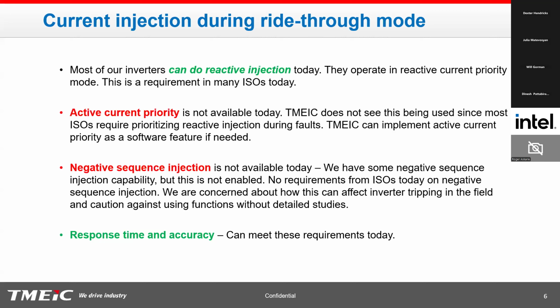On response time and accuracy, there are accuracy requirements, I think plus 10% and minus 2.5%, as well as a time requirement for these functions, I think 2.5 cycles to 4 cycles for steady state. We believe we can meet these requirements today with our existing inverters, even in the field. We don't have any problems in that regard on existing or new inverters. Whatever I'm saying about current injection applies to most of our existing inverters in the field as well as newer inverters.